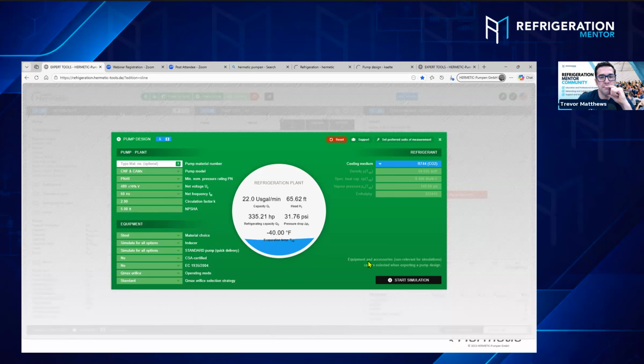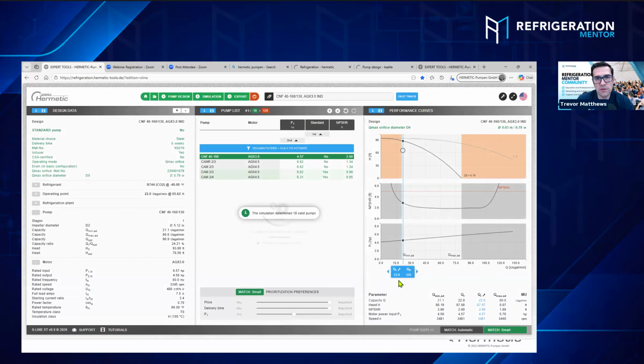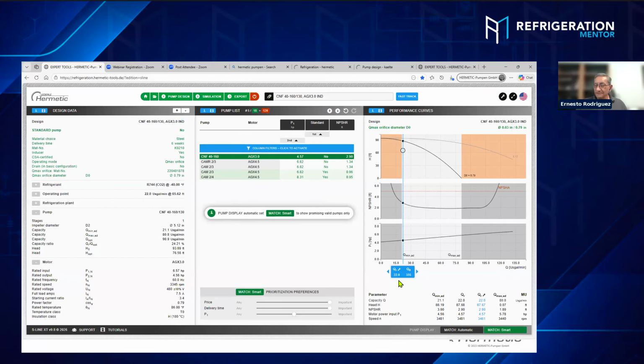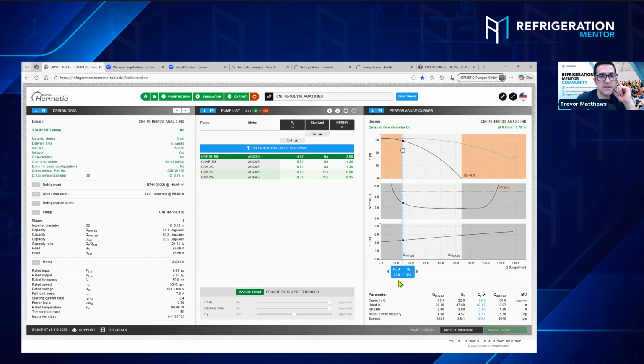Now we have an option of Qmax, flow control valve, or a frequency controller. I want to run the three options for you to see exactly how it is going to work. I want to go to the orifice, Qmax. We run the sample right now. The program is selecting which pumps we need. Inside this program there are different units, so if you want to do it in cubic meters or gallons per minute, you can change all that. I will explain it in a few minutes when I go back to the main screen.